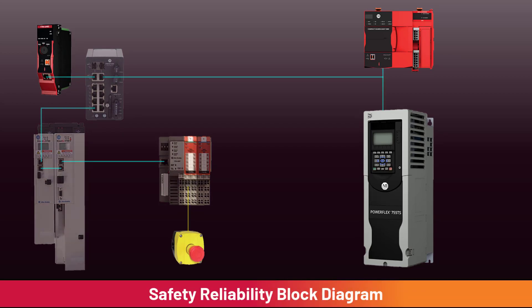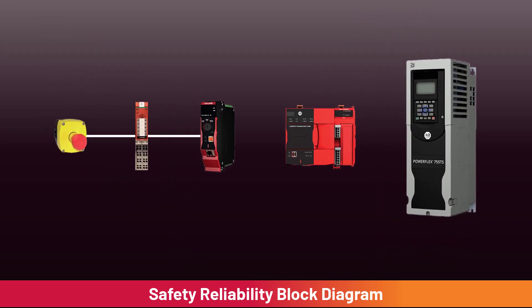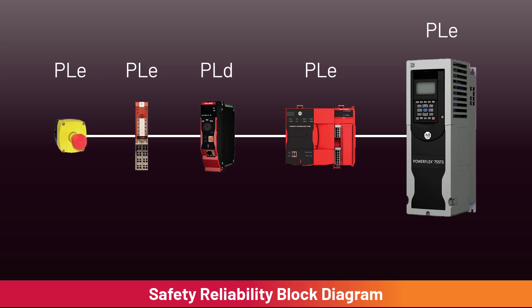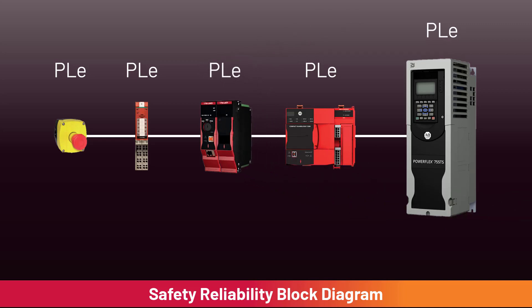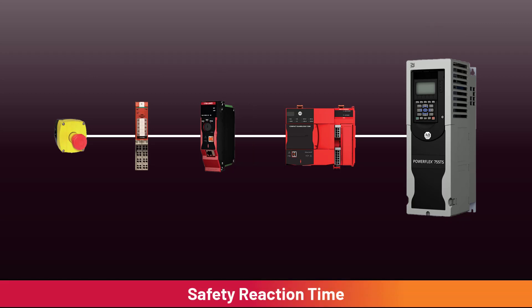Let's review the emergency stop safety reliability block diagram for the combined system. The emergency stop and safety inputs have a PLe rating, but the single GuardLogix 1756-L84ES controller is rated at PLd. The new Compact GuardLogix system uses a PLe-rated Compact GuardLogix controller, and the PowerFlex 755 has a PLe-rated motion monitoring and safe torque off. The PLd controller producing the E-stop signal will limit the overall safety function to PLd. If PLe were required, a safety partner would need to be added to the 1756-L84ES GuardLogix. An additional consideration is safety reaction time.